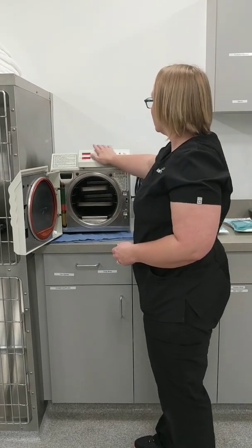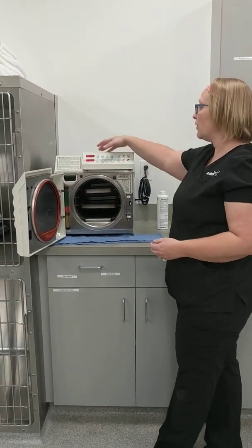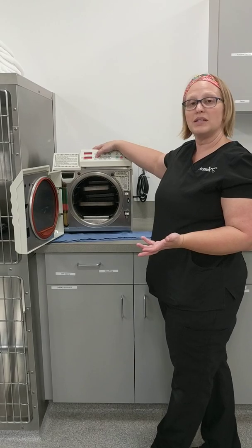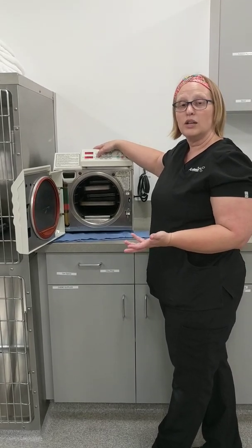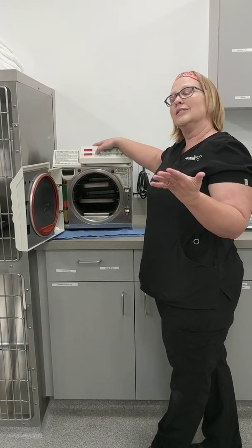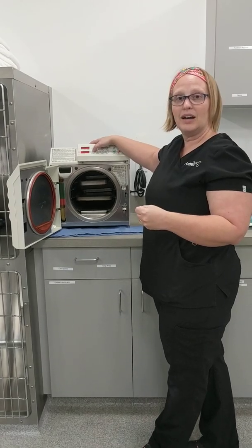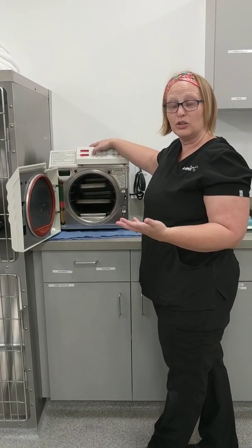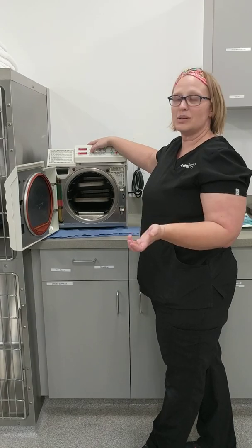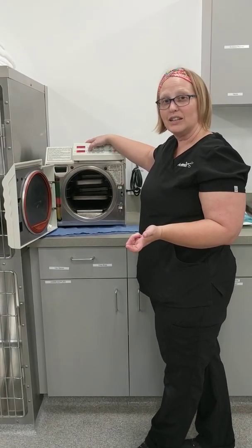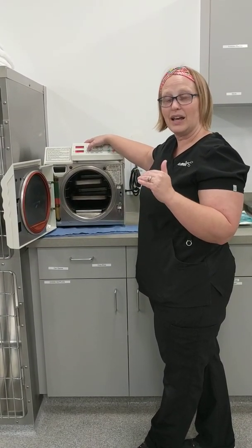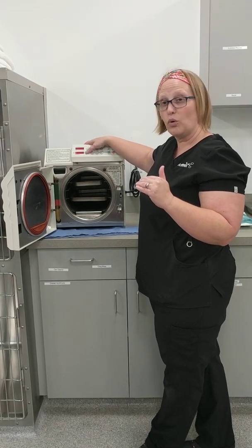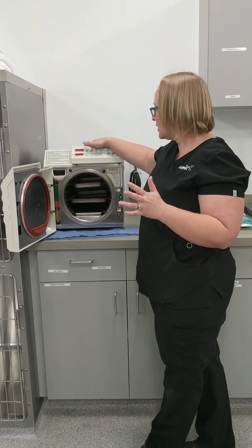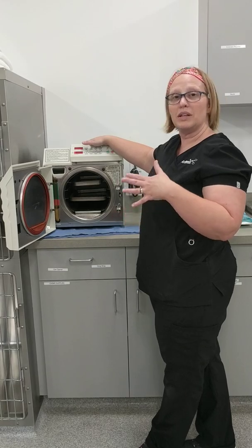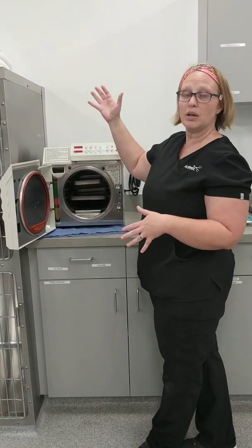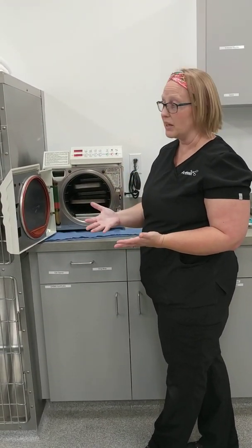The autoclave settings for this autoclave specifically, we have an unwrapped setting, so basically if you're using an instrument, you need it to be cleaned, but not completely surgical sterile. You can use this setting. The setting runs about 270 degrees Fahrenheit. Once it reaches that point, it maintains that steam heat level for about 3 minutes. That 3-minute point comes through, you'll hear a pop, steam comes up, and it starts the cooling process from there.